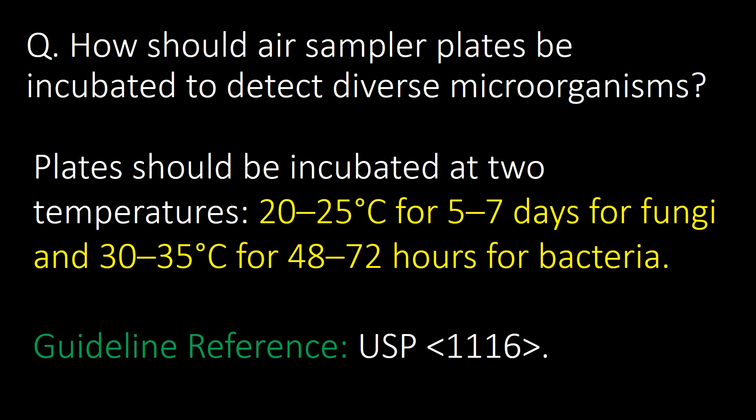How should air sampler plates be incubated to detect diverse microorganisms? Plates should be incubated at two temperatures: 20 to 25 degrees Celsius for 5 to 7 days for fungi, and 30 to 35 degrees Celsius for 48 to 72 hours for bacteria. Guideline reference: USP chapter 1116.